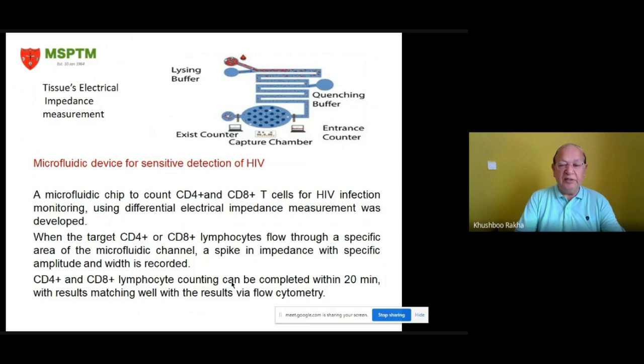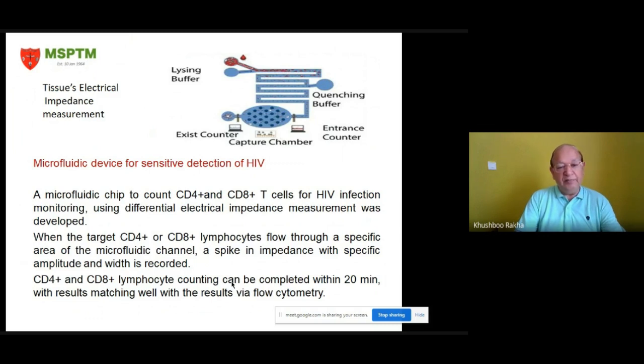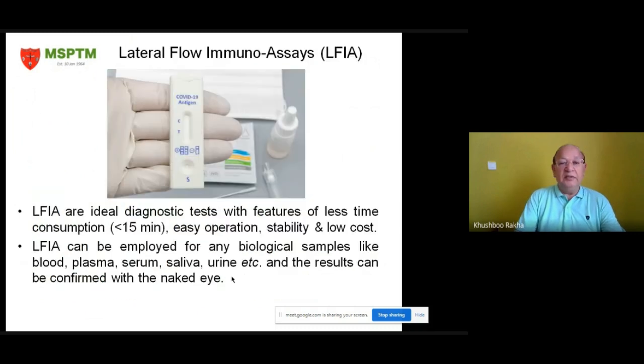A microfluidic device for sensitive detection of HIV was also developed — a microfluidic chip to count CD4 and CD8 T cells for HIV infection monitoring using differential electrical impedance measurement. When target CD4 or CD8 lymphocytes flow through a specific area of the microfluidic channel, a spike in impedance with specific amplitude and width is recorded. CD4+ and CD8+ lymphocyte counting can be completed within 20 minutes, with results matching well with flow cytometry.